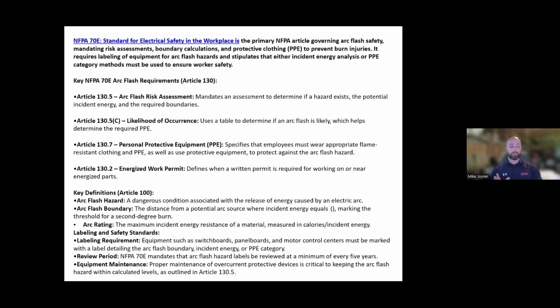And the way this whole process works is, if you have an existing arc flash study and it's beyond the date, then we tend to work with whoever built the actual model. If there are multiple different engineers out there, we work with them. We reach out to them. We do all the data collecting. We go in there, dissect all the electrical equipment, and update the one lines as much as we can. If there are no one lines, then we draw and create brand new one lines for each of the buildings. Then it gets sent out to the engineer. They do their engineering, and we go through the process with you, label everything, and make sure everything is proper, so you are compliant and everything is being maintained properly per your arc flash.